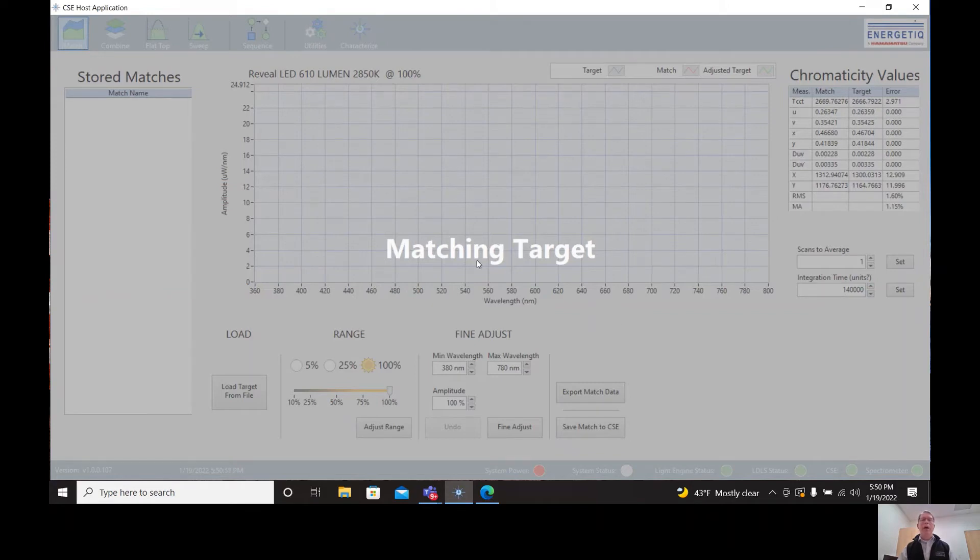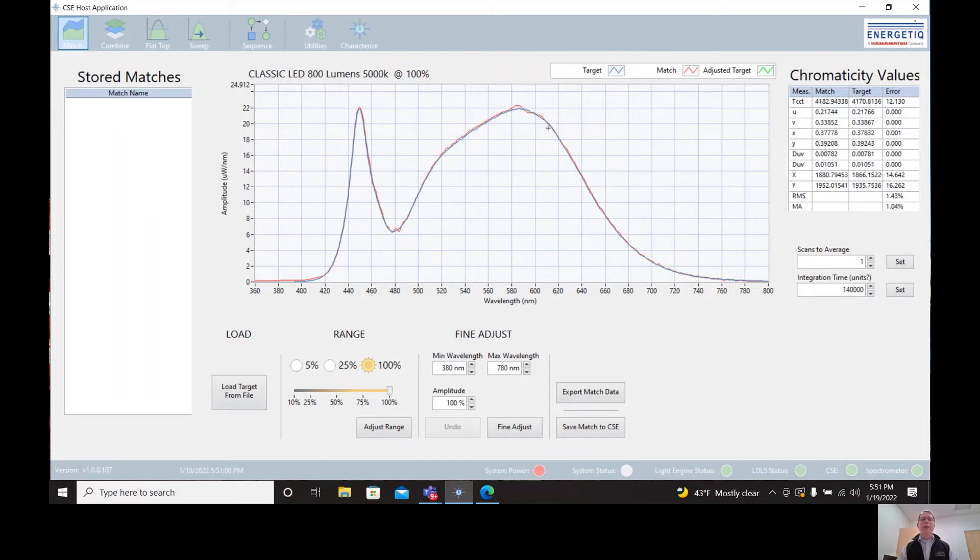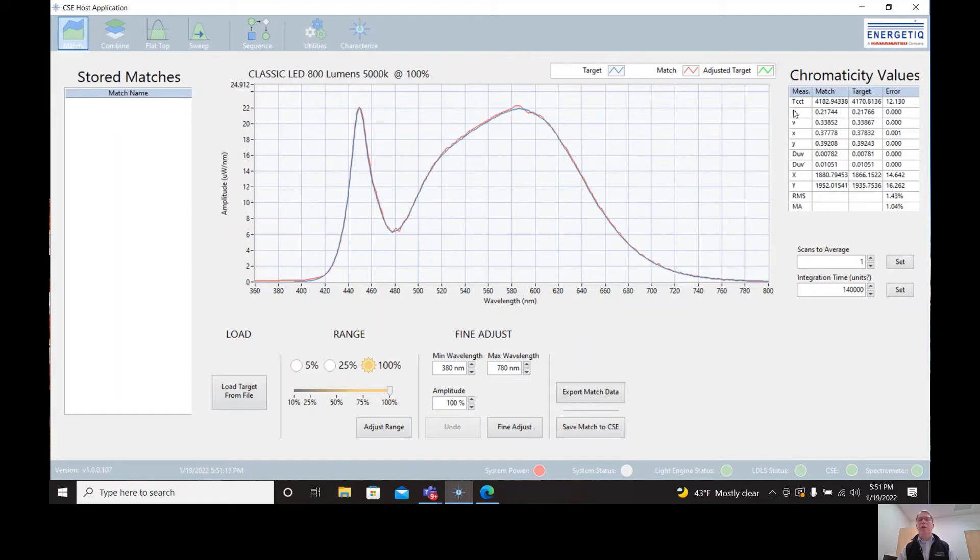In the background, the CSE matching algorithms are performing the match to this target. Now we see an overlay plot in which the blue curve is the target and the red curve is the match. And we can see visually that the match is very accurate. On the right side of the screen, there's a table of numbers that quantify the accuracy of the match in terms of color temperature, color coordinates, and the overall RMS error.